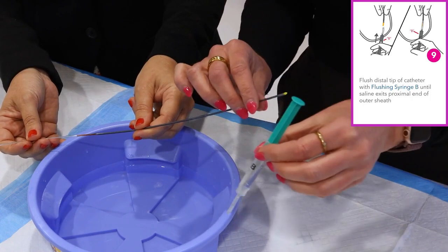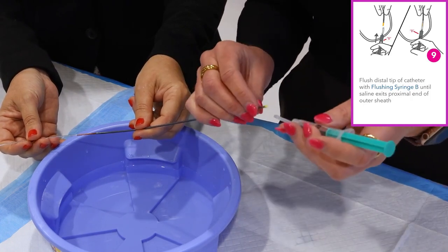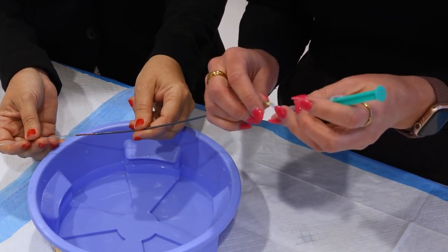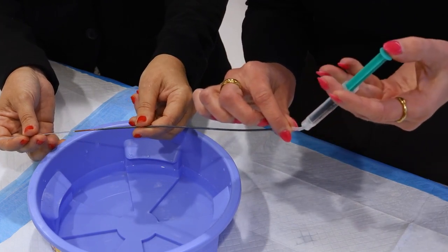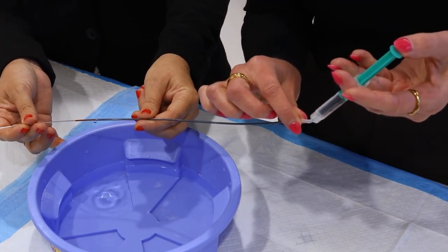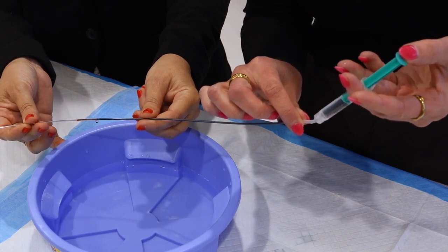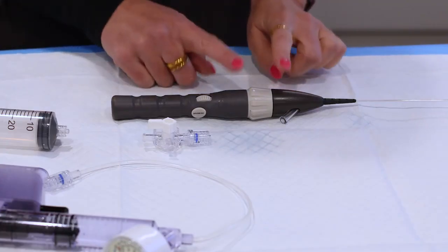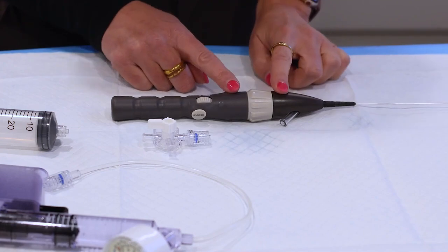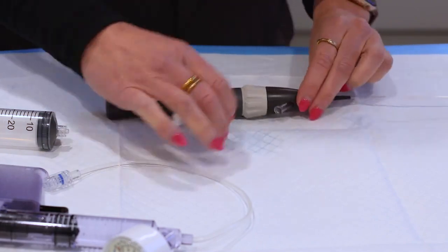Using syringe B, we're going to flush the distal tip of the catheter until we see saline exiting the proximal end of the outer sheath. Next, we will prepare the balloon. Attach a stopcock to the balloon inflation port of the catheter.